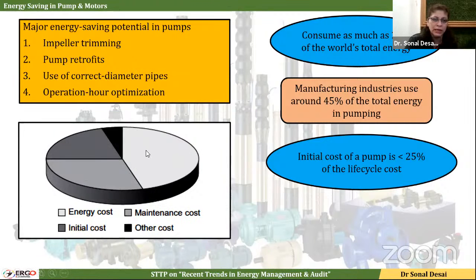As I just said, energy cost is a major factor when we talk about pump operation. So this is an indication of energy cost, while this is the initial cost. You can see that it is very small. Again, it depends on the capacity, that is the rating of the pump, but still for almost all cases, the initial cost is very, very small compared to the operation cost. Hence, we should not target this so much, but we should target this, because this is what we are going to pay in the long run, and all payback issues are related to this.